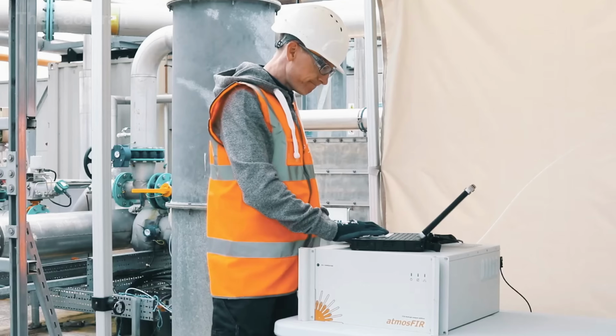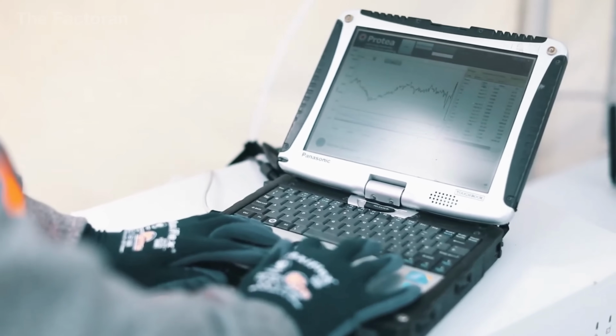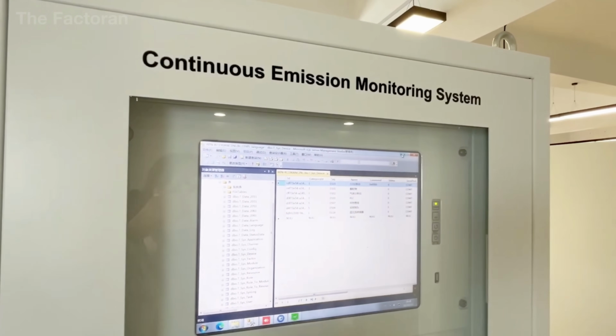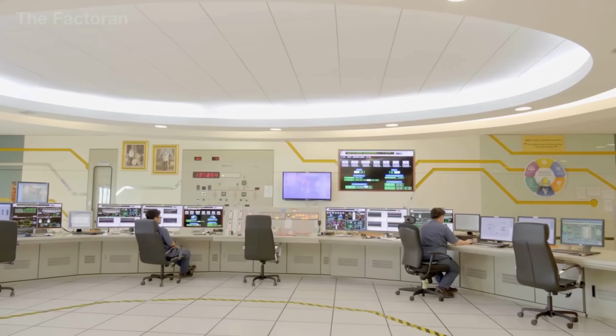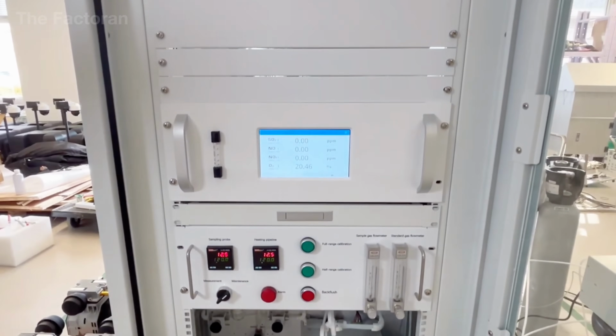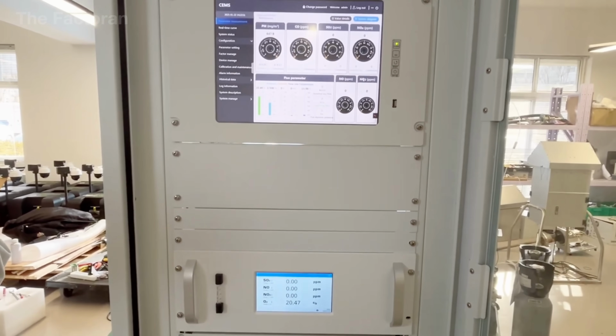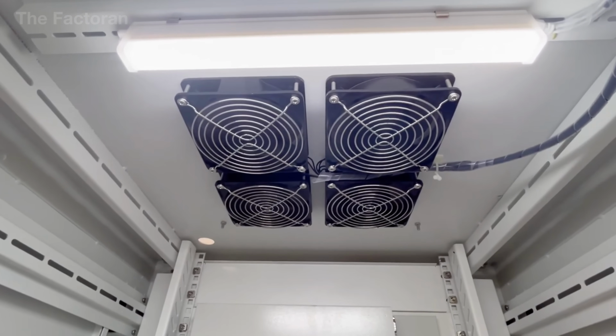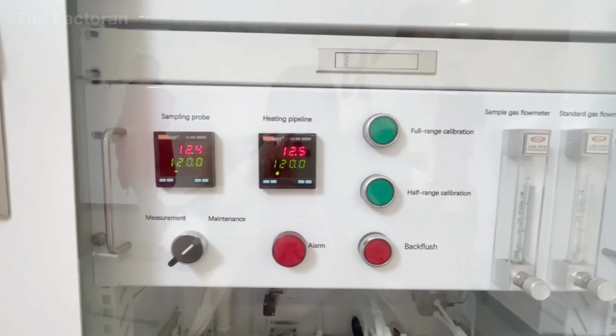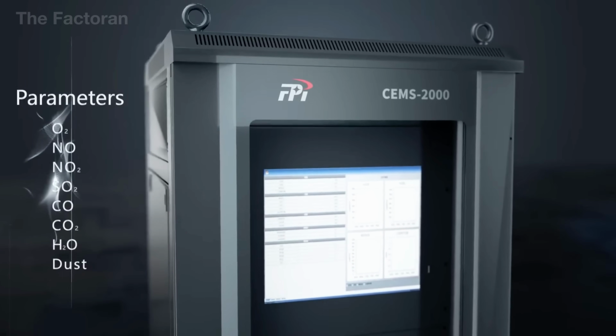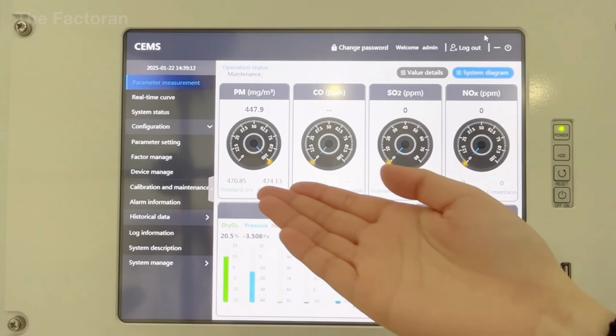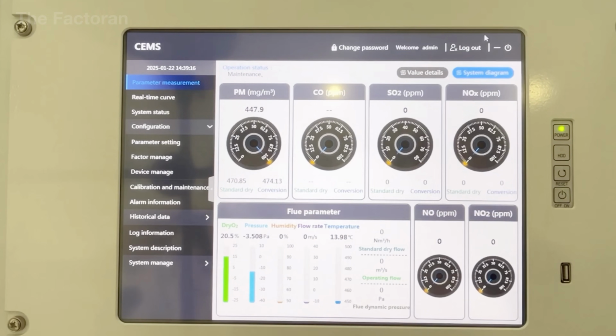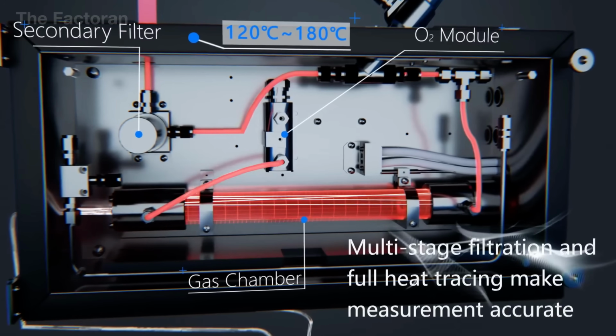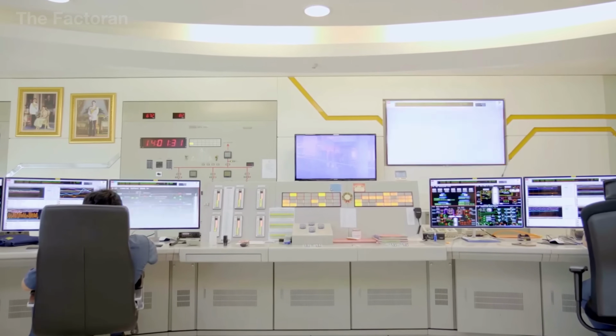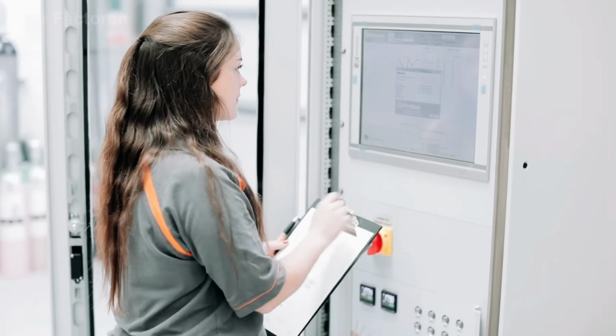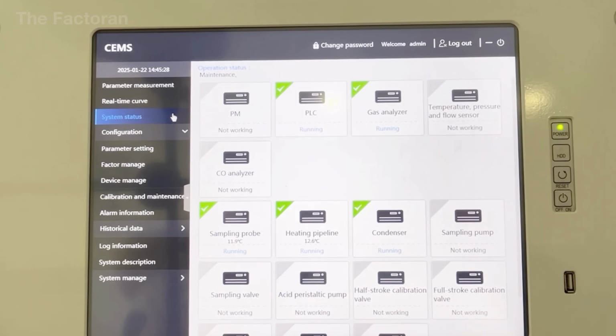Before the purified gas is released through the smokestack, the entire emission control system is monitored by CEMS, Continuous Emission Monitoring System, an automated network of instruments operating 24 hours a day, 7 days a week. The system is installed directly on the smokestack or at the final exhaust duct using infrared, ultraviolet, laser, and electrochemical sensors to continuously analyze every component of the gas stream. CEMS tracks concentrations of SO2, NOx, CO, CO2, and O2, along with fine particulate matter, PM, temperature, pressure, and flow rate. The data collected by the sensors are processed by a central controller, then transmitted to the distributed control system, DCS room, and simultaneously reported online to environmental authorities as required by law.